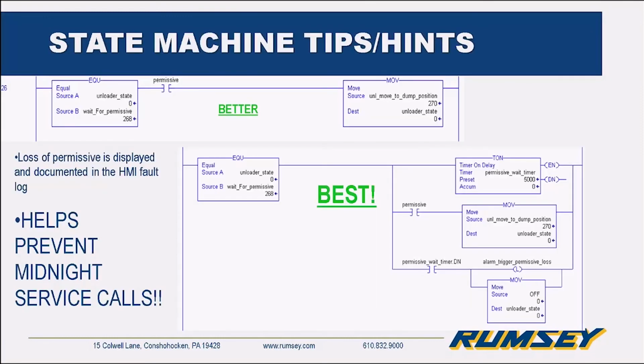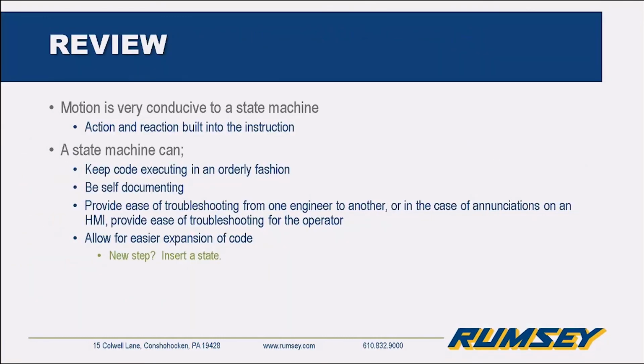So a little bit of review. Motion is very conducive to a state machine. Action and reaction is built into the instruction. A state machine can keep code executing in an orderly fashion. Be self-documenting. Provide ease of troubleshooting from one engineer to another. With thorough programming, such as the watchdog timer, keep a machine in a state until your reaction is met or until the watchdog times out, and then we have annunciation on an HMI.